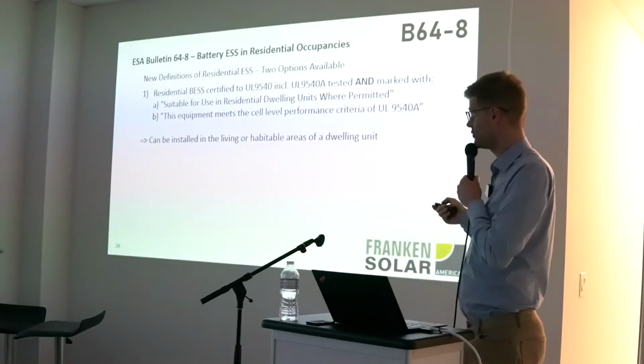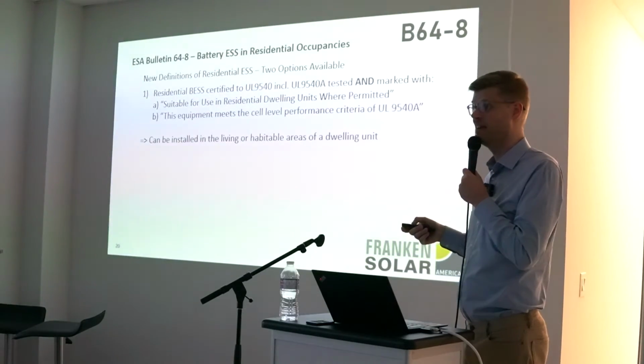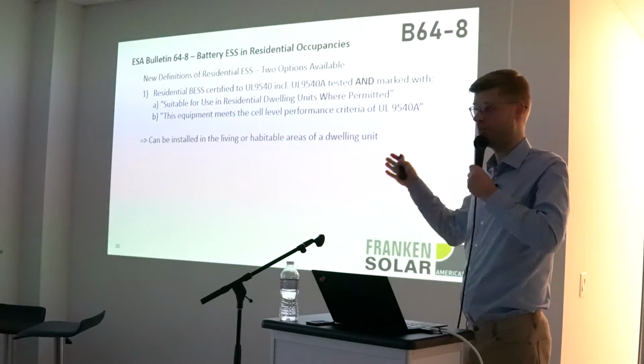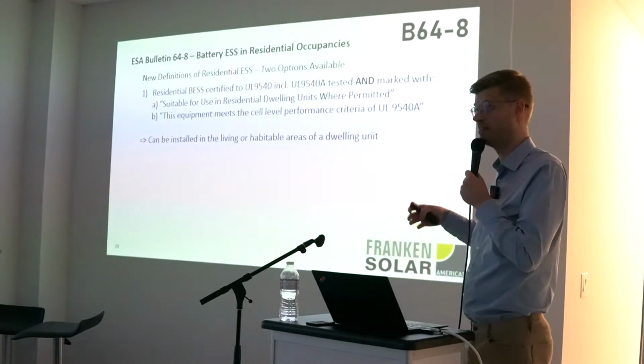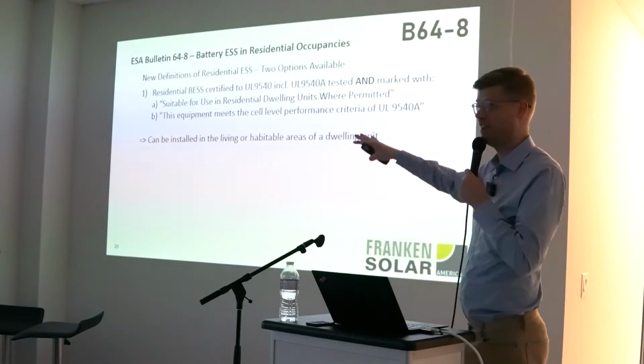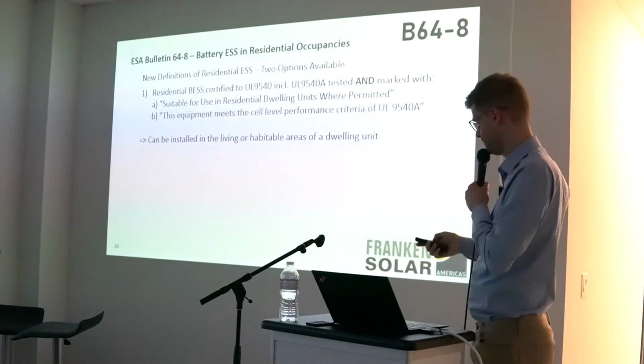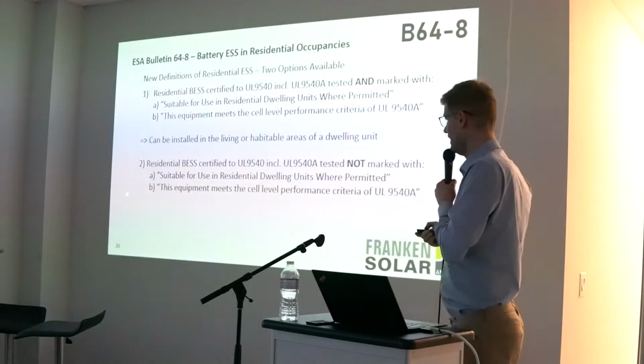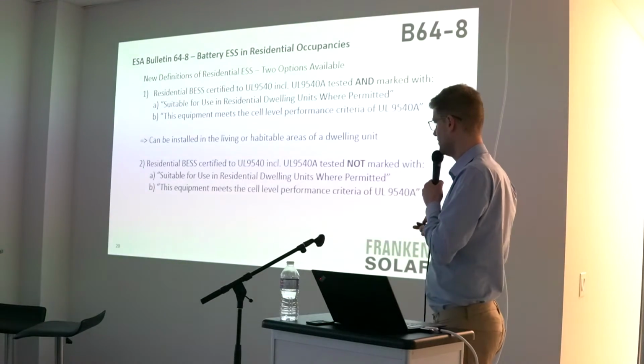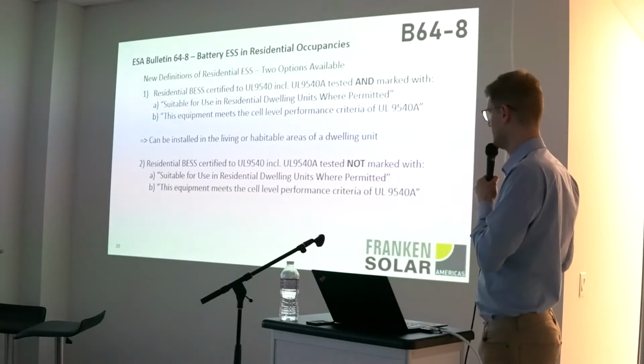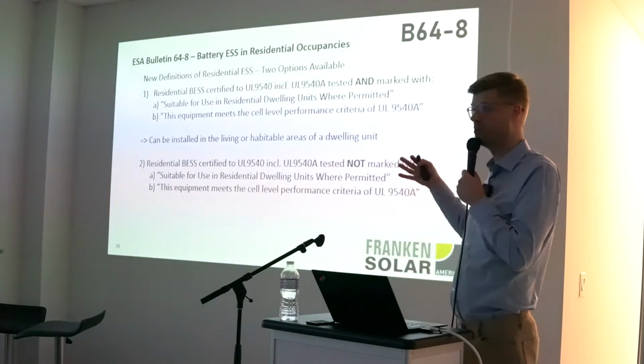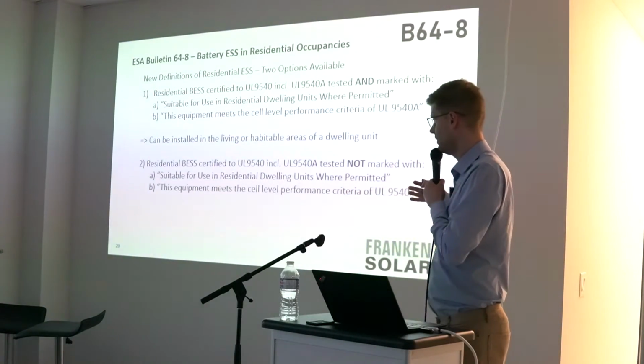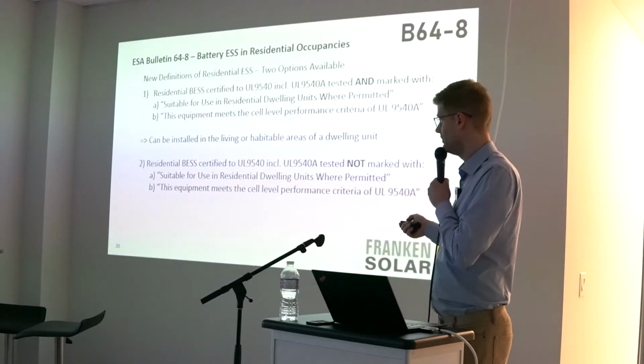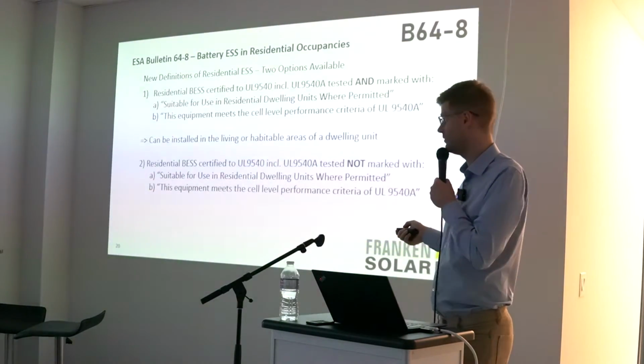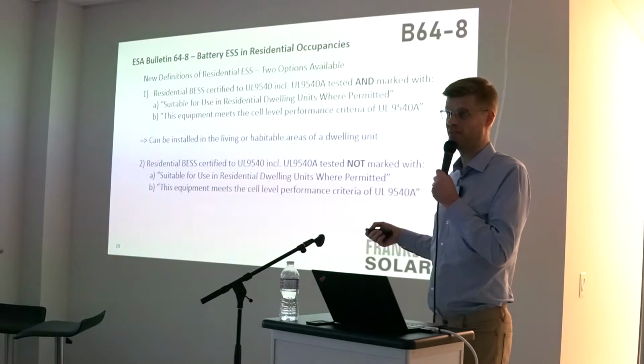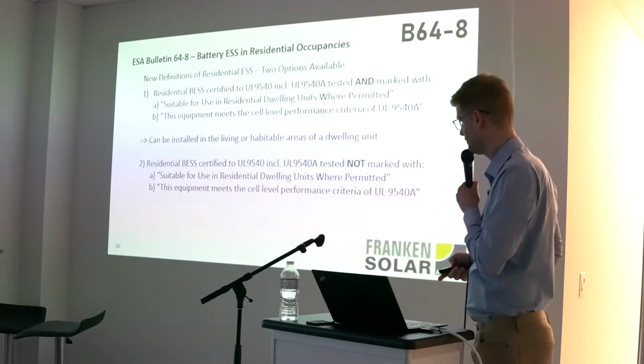There are no restrictions because you have that cell level performance criteria, and it would be that toaster analogy, that you can plug it in wherever you want because there's no hazard coming from that system. Again, unfortunately, this category is off the table. It does not exist. Second option. You can have the same system certified, but it's not marked with these things because most likely your battery manufacturer or your system provider has not passed the performance criteria of the cell level, and they may or may not have that additional sentence on the type label.